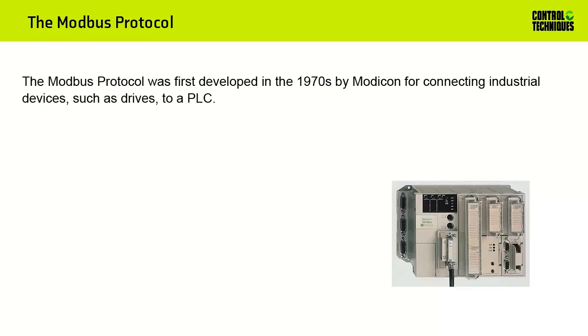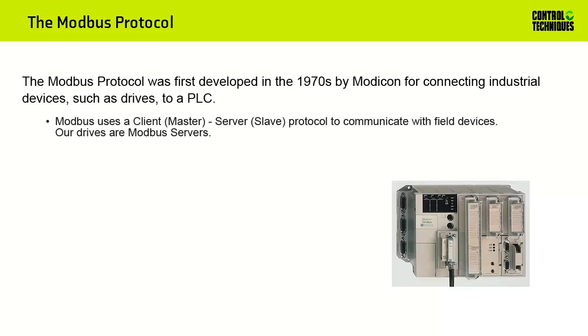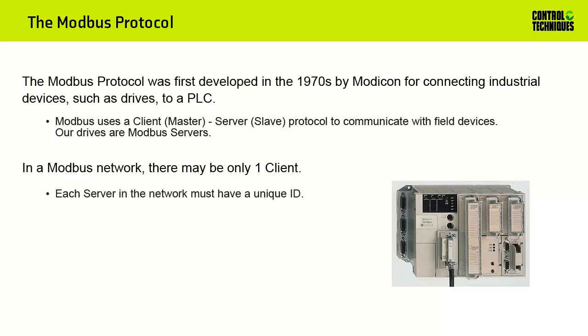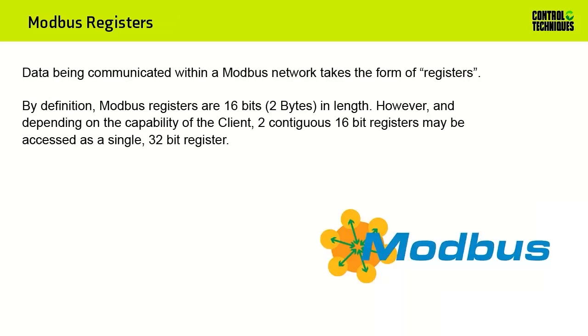The Modbus protocol was first developed in the 1970s by Modicon for connecting industrial devices, such as drives, to a PLC. Modbus uses a client or master, server or slave protocol to communicate with field devices. Our drives are Modbus servers. In a Modbus network, there may be only one client or master. Each server or slave in the network must have a unique ID. Data being communicated within a Modbus network takes the form of registers.